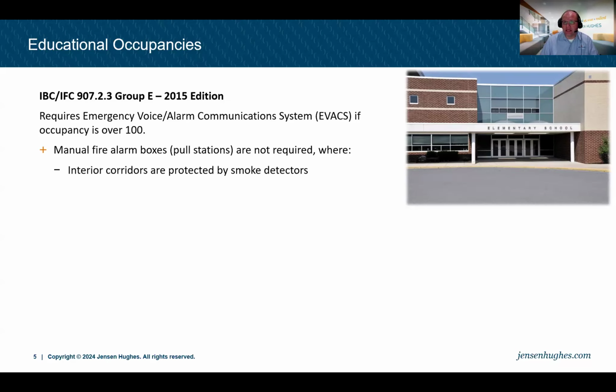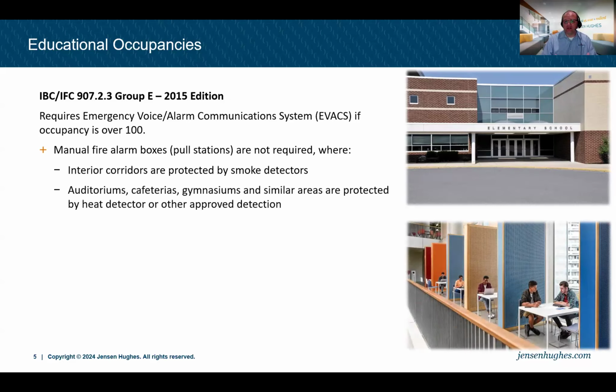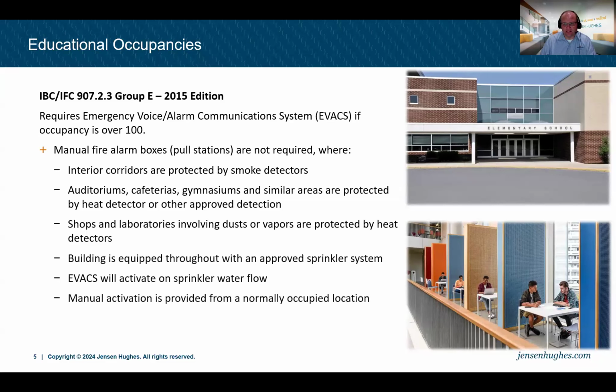For instance, we need smoke detectors in interior corridors. We have to have auditoriums, cafeterias, gymnasiums, and similar areas protected by heat detectors or other approved detection devices. We need the shops and laboratories involving dust and vapors to be protected by heat detectors. And that makes sense because errors can lead to life safety situations in those shops and laboratories. And we need a building that's equipped with an approved fire sprinkler system, which many of our educational occupancies didn't have in years past. That sprinkler system needs to activate the voice fire alarm system on any kind of sprinkler water flow. So we see some of this progress to be able to communicate with, in this case, students and occupants of a K through 12 facility.